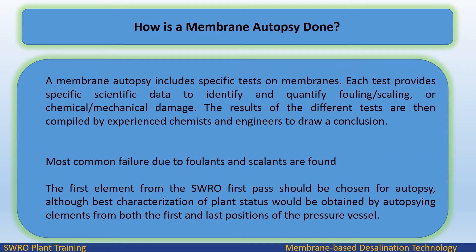Identifying the problem at an early stage can help save huge costs before excessive damage renders membranes useless. A membrane autopsy includes specific tests that provide scientific data to identify and quantify fouling/scaling or chemical/mechanical damage. Results are compiled by experienced chemists and engineers to draw conclusions. The first element from the SWRO first pass should be chosen for autopsy, although best characterization would be obtained by autopsying elements from both the first and last positions of the pressure vessel.